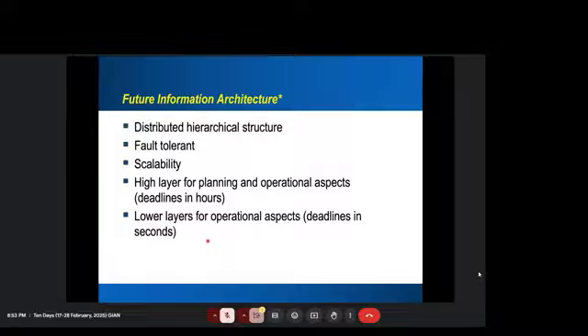Protection right now is not coordinated. It will only be coordinated between 2 or 3 relays, which is okay, better than taking a decision without any coordination. But because of this, most blackouts happen. Why? Protection is keeping us safe, but it does not have a system view. It does not know that I am making a decision because I see a fault, but why do I see a fault? Where is the fault at the system level? And if I open it, is it going to help or not? It always helps the component it's isolating, but it may not be helping the system.